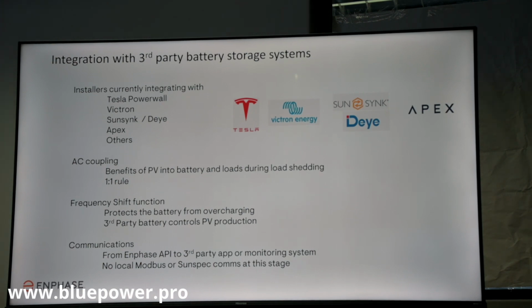And the way you do that - same with Sunsynk, Deye, and Apex, which Rubicon is selling - is through AC coupling. So what is AC coupling? You can plug in microinverters anywhere there's an AC network, on the nominal side, the grid side, but when the grid goes down, the micros are going to go down too.